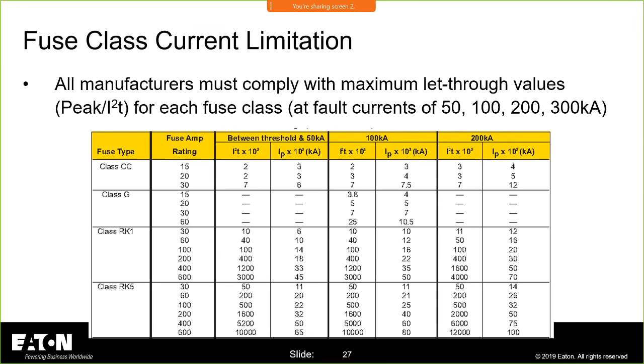So here's something I've said before, and I'll say it again. You know what fuses eat for breakfast, lunch, and dinner? The more of it, the more they love it, and they never gain weight. Current. They love current. They eat it up. The more you give that fuse, the more efficient, the better it's going to work for you. And in most cases, you want to feed that fuse current. You know, the whole concept of reduce your currents, reduces incident energy. If you're using fuses, you want to feed that fuse current. The more of it, the better off you are. It will act so fast. It will reduce the magnetic forces, and it will solve a lot of your arc flash and short circuit capability concerns, just as long as you're not working in that long time region.